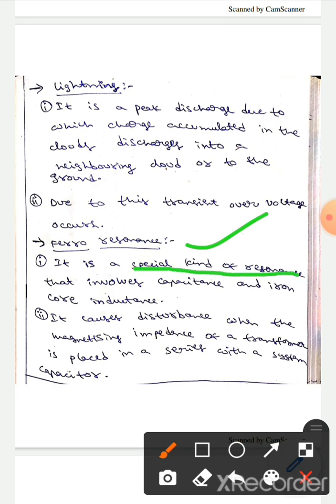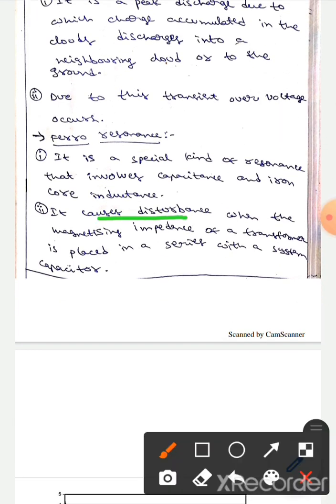The next source is ferro resonance. It is a special kind of resonance that involves capacitance and iron core inductance. It usually causes disturbance when the magnetizing impedance of a transformer is placed in series with a system capacitor.